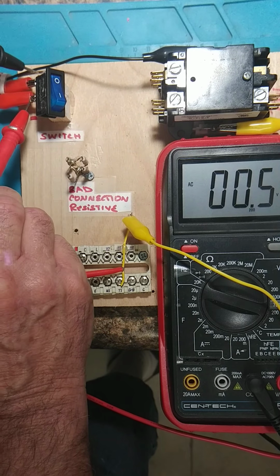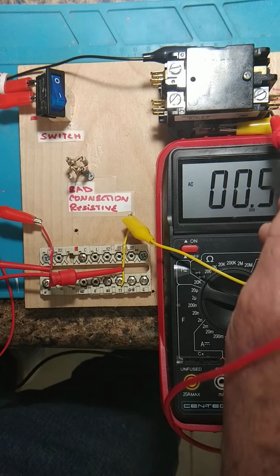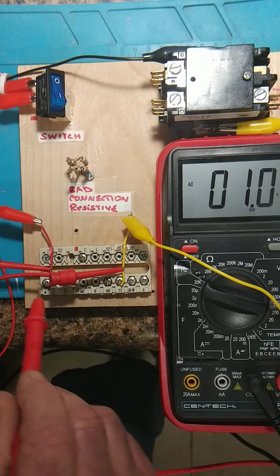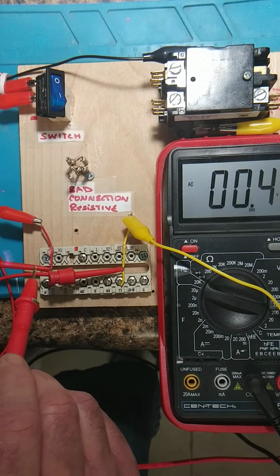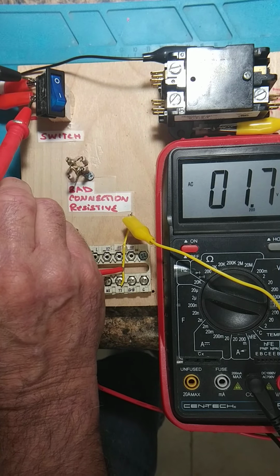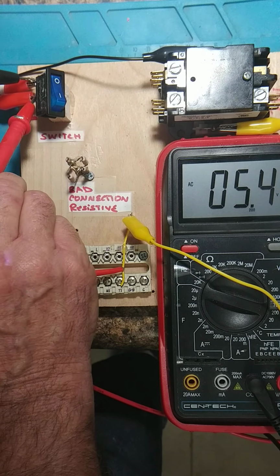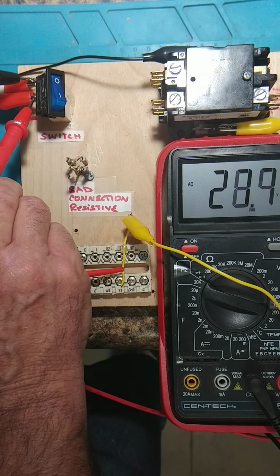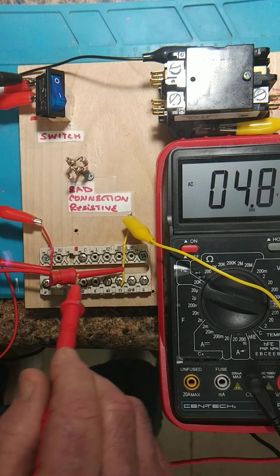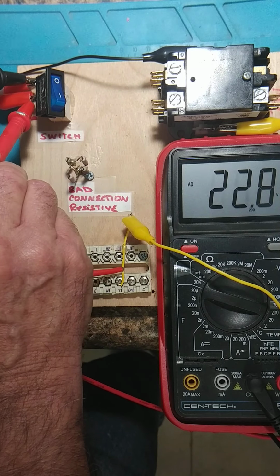So actually, if I check across here, because I've got a closed circuit, I should have 24 volts because common is going to be felt through Y, through my thermostat, which is calling, back to this point. This is my open. So if I check from here to here, I should have 28, and I do. It's because this is where my open is. This is where I'm dropping voltage. This is actually common being felt through my thermostat that's closed. It's calling for cooling.